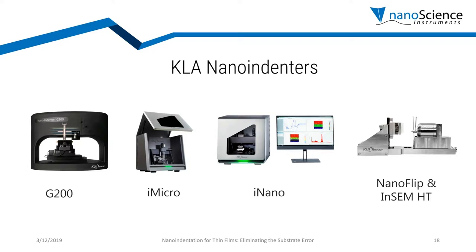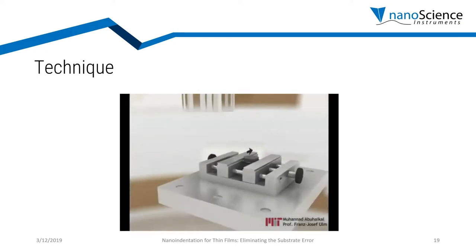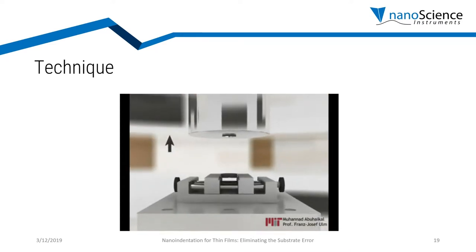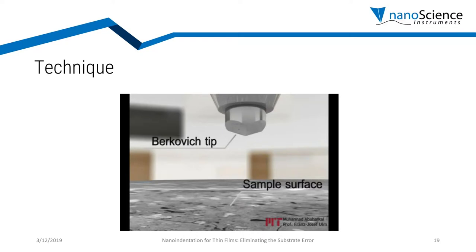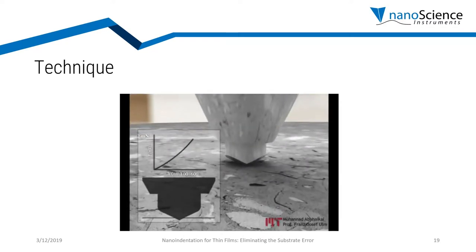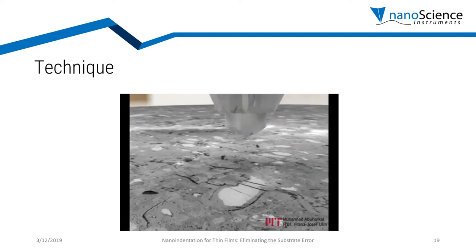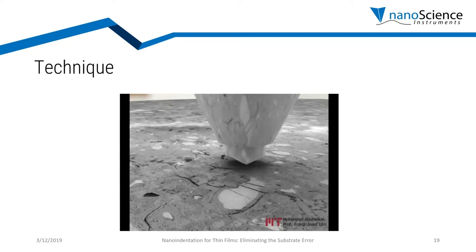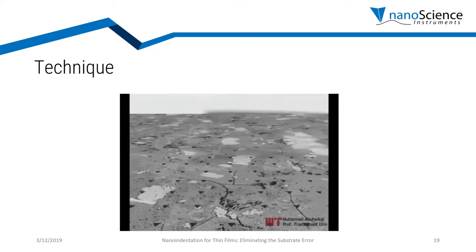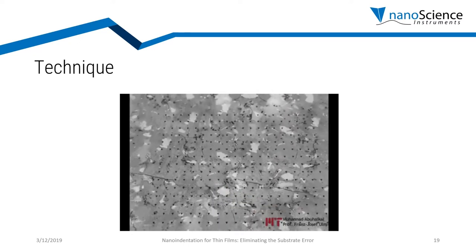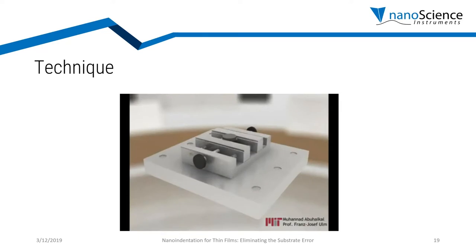If you are not familiar with nano indentation, the basic process is this: you have a sample and you place an indent using a tip — here we use a Berkovich tip — and you move the tip onto the surface and penetrate into it. While doing so, you measure the load you are applying and the displacement it produces into the surface. The process is very fast, done in seconds, allowing you to produce hundreds of indents for excellent statistical data.